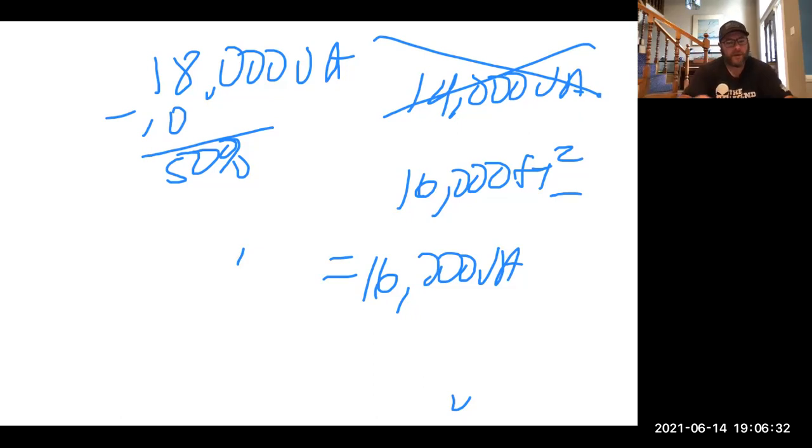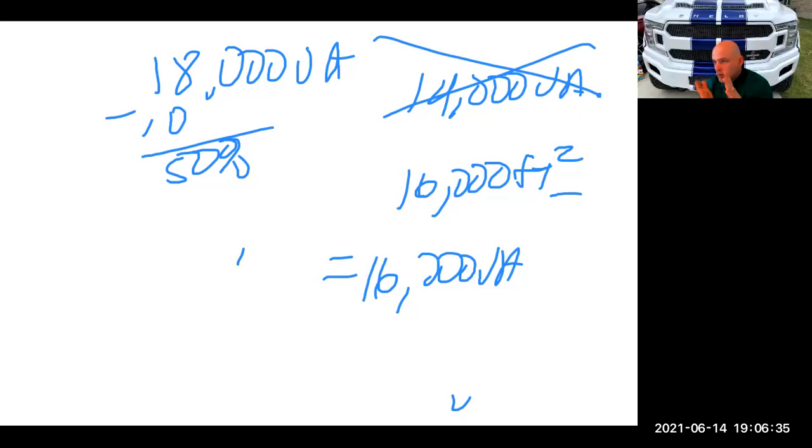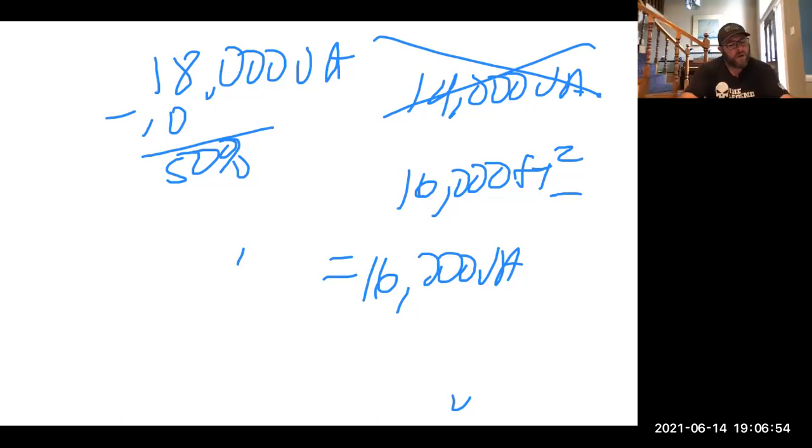All right. And that's really, other than multi-wire conductors would be considered a single wire. So if they give you a 16-3 or something, that's just a single wire. And if you've got a ground wire in there too, then that's just 2 wires, which is a different column for fill value, because there's just 2 wires at that point. Right. Why, I guess is a better idea. Why did the National Electrical Code decide that it was fine to run Romex in conduit?